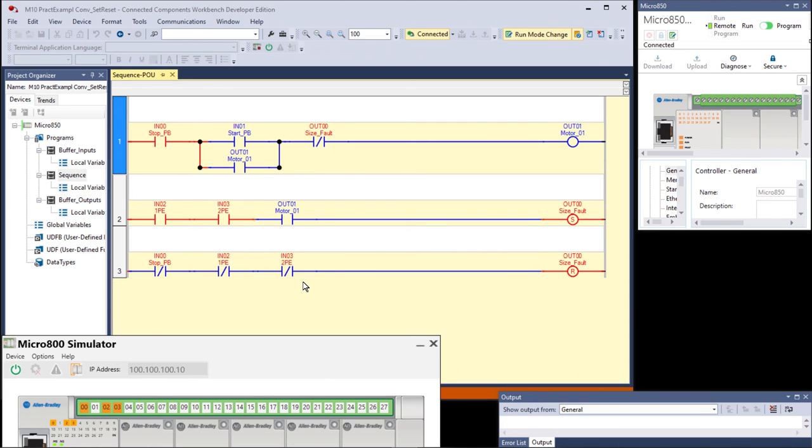So in the logic we did have before, without the addition of these two true if off anded photo eye 1 and 2, you could clear the fault without clearing the photo eyes, but it will immediately fault on start. And I guess you could argue that doing it this way saves production time because the operator doesn't hit the stop button, think it's reset, and then hit the start button, and it doesn't run, and they're standing there thinking, okay, now what's going on? They call maintenance. The maintenance guy gets there and he looks at it and says, you gotta be kidding me. This is with the previous logic, not this logic. And actually, even with this logic, if they don't know they have to clear that carton, then they're never gonna get it running again. Okay, let's take a look at something else.